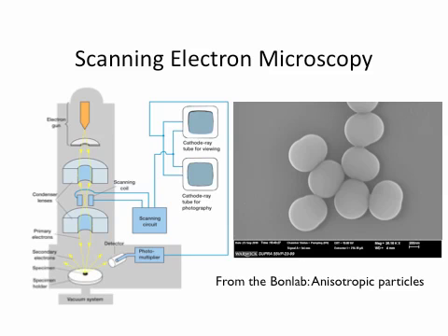And what's really important is that the specimen is conducting. So you either coat your sample with a conducting material, so use plasma sputter gold over it, or platinum or palladium, or a thin carbon film, or alternatively you put a very, very thin sample on a silicon wafer, which is conducting, and then you are able to image as well.